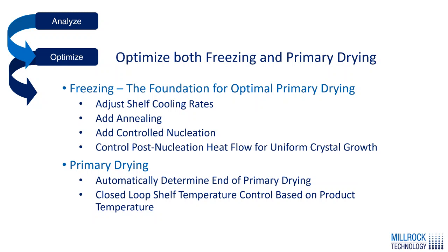This is important because during nucleation, only about 10% of the available water creates ice crystals, so 90% of the freezing takes place post-nucleation. In primary drying, we can determine the end of primary drying automatically using pressure differential between the capacitance manometer and the Pirani. We can also do closed-loop temperature control, which we call auto-dry, where we control the shelf temperature based on the product temperature and maintain the product temperature below its critical point, thus optimizing the primary drying cycle.